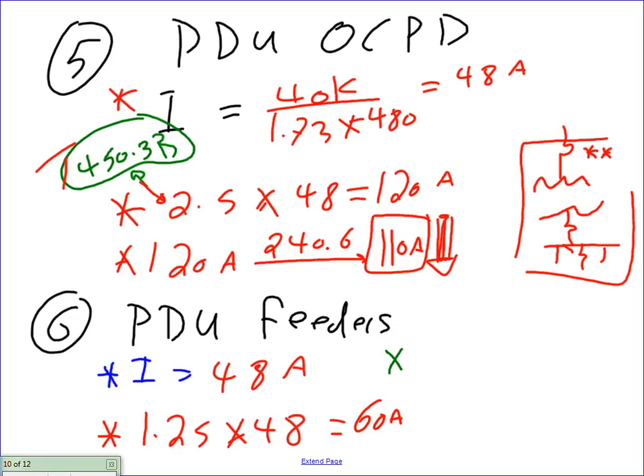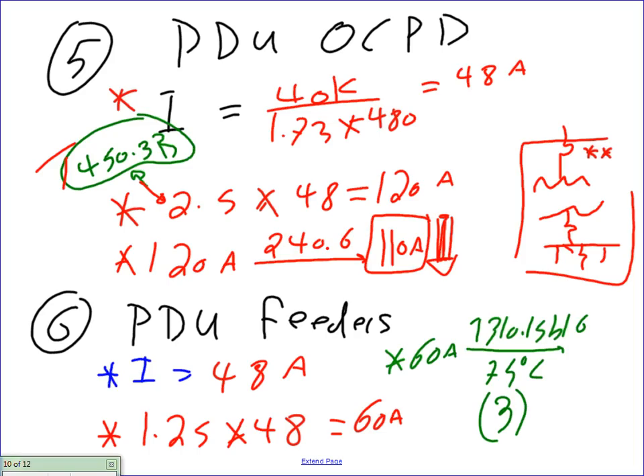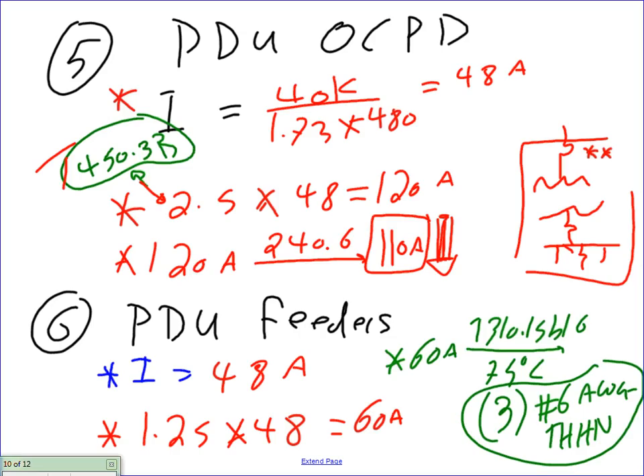Then you take your healthy 60 amps and you take it to table 310.15(B)(16), 75 degree column. How many conductors do we need for this baby? 3 conductors. Why 3 conductors? I don't need a neutral yet. I'm still carrying 480. 3 conductors, and what size? Number 6 AWG THHN. Done. 3 conductors, number 6, coming out of the UPS to every PDU. We have 2 of them, redundant, so they're all going to be the same size. I did 1 PDU, guys. What do you think the other PDU is going to be? Redundant. This is what you guys are going to be doing for your project when you size the PDUs, exactly the same criteria. Any question about number 6 before I move to number 7?